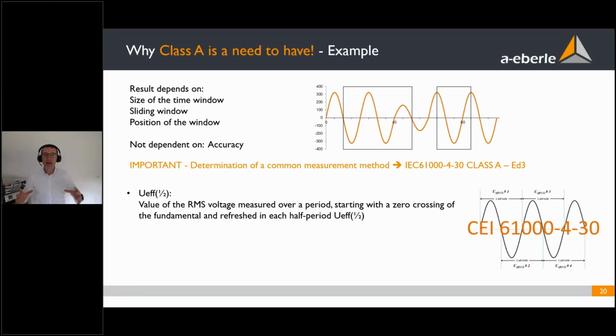There are many other values which are completely defined, also defined over external influences like temperature, like the frequency. Because if you are measuring over zero crossings, it's clear that the frequency will also influence your measurement results, and this has to be defined too.